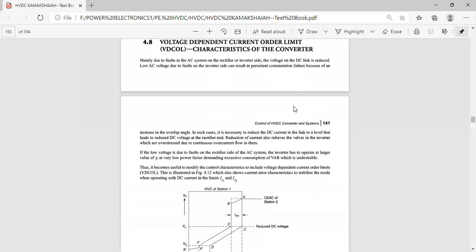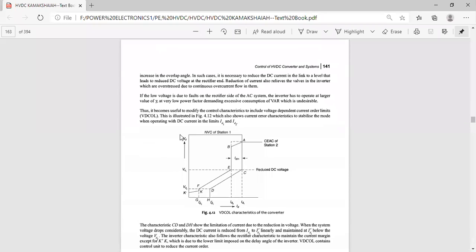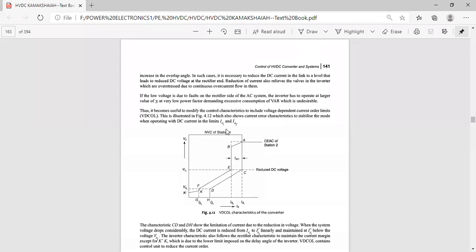Now coming to the voltage dependent current order limit. This is the rectifier station. Id1 is the current at the rectifier, and this is the inverter characteristic with the sub-slope. Id2 is the current of the inverter, and Idm is the current margin: Id1 minus Id2 equals Idm.